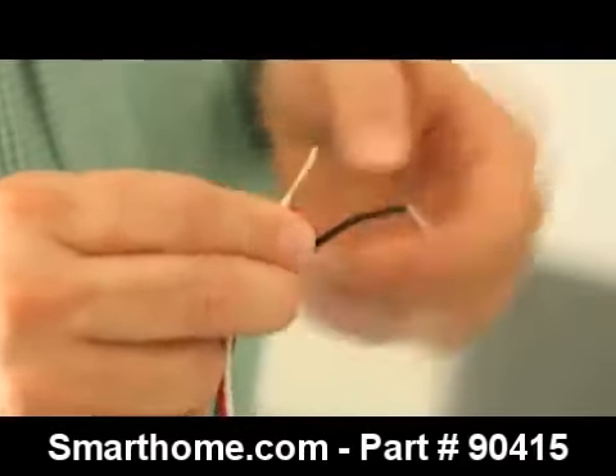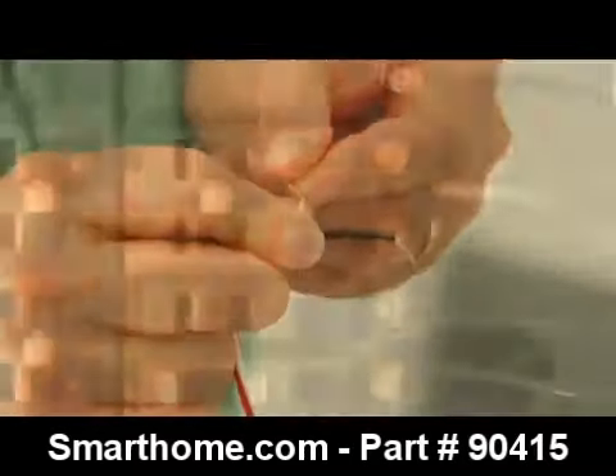Even though the main breaker has been turned off, please note that the conductors feeding the main breaker are still electrically charged. For ease of installation, once you unravel the power cable, bend the tinned wire at a 90-degree angle. It's now time to connect the black and red wires from the MTU power cord to a spare 2-pole circuit breaker in the panel.